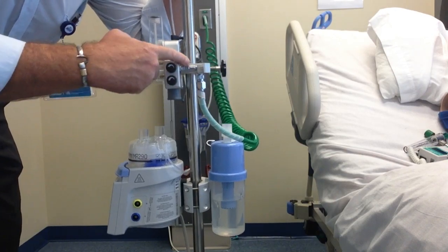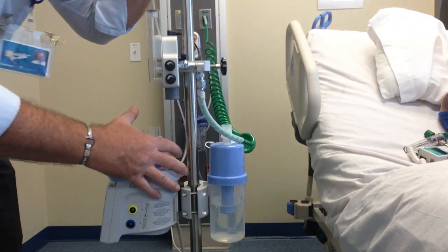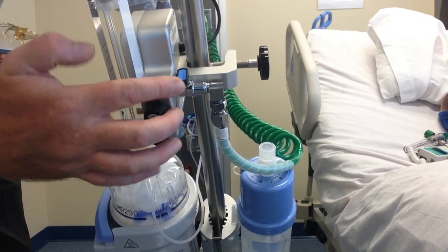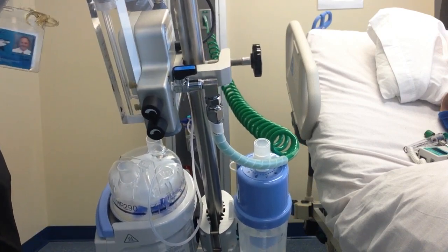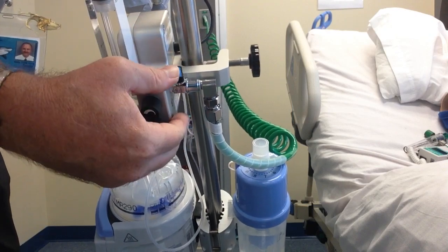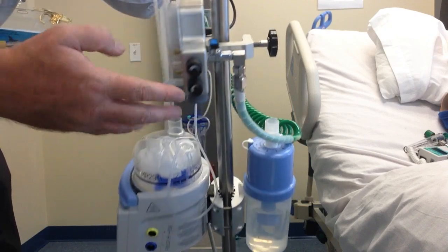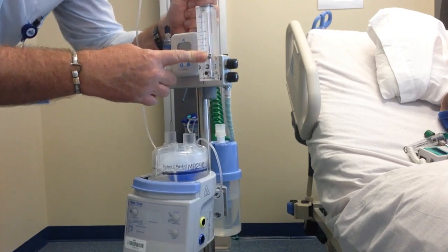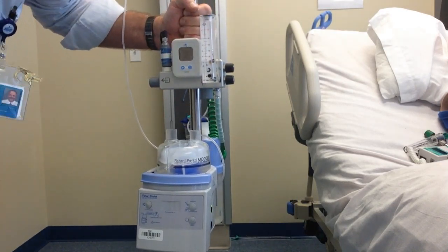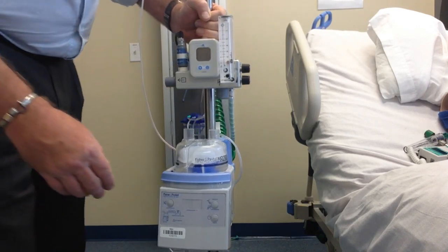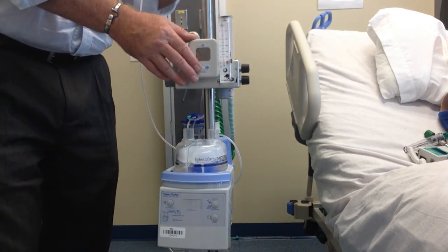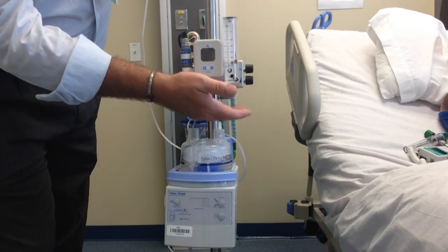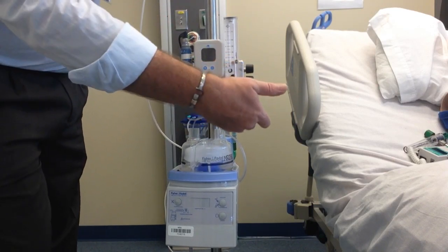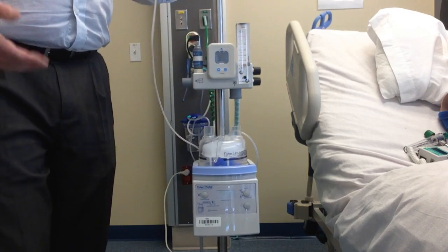You have a main gas on-off switch. Let's see if we can get a better picture. Right here. Just like a zone valve. That's on, that's off. On, off. We have a high flow meter that goes up to 60 liters per minute. Typically you're going to be running this about 30 to 50 liters per minute. We have our oxygen analyzer, we have the patient output, and we have the input from the room that this device will suck up room air in order to dilute your oxygen down to the exact FiO2.